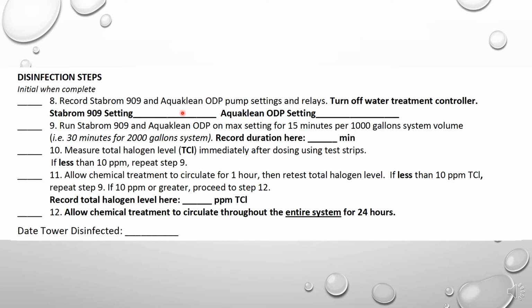So this is where you write your bromine setting, this is where you write your biodispersant setting on those pumps, and then you want to turn off your treatment controller. You're going to raise those pumps to max setting, and you're going to pump for 15 minutes per 1,000 gallons, and you record the duration there. Then you're going to measure your total halogen using test strips.